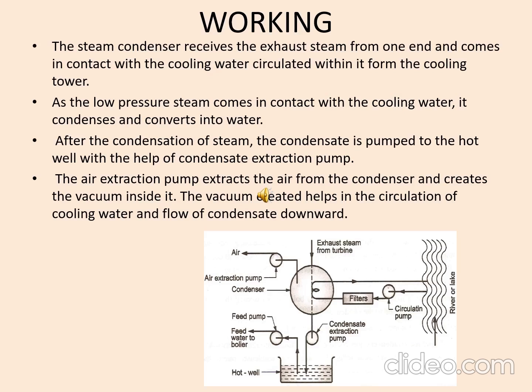Another air extraction pump is there inside the condenser, which can extract the air from the condenser. If air is extracted, then what will happen? You know that a vacuum will be produced. The vacuum will help circulate the cooling water and the flow of condensate downward. So a vacuum is required, and for making the vacuum, an air extraction pump is required, which can extract the air from the condenser.